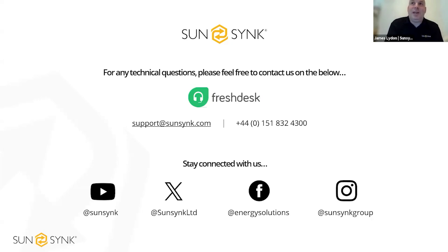But as I mentioned at the beginning, we have that dedicated UK tech support team. I always say to new installers, if it's your first install, reach out to us when you're on site, when you've got the system installed and your comms connected to it so we can remotely access it. Say to our support team, "Look, it's my first install, please can you log into it, check I've set everything correctly, make sure we've got the correct BMS comms, and the correct system modes selected," and they will go in and support you in doing that.